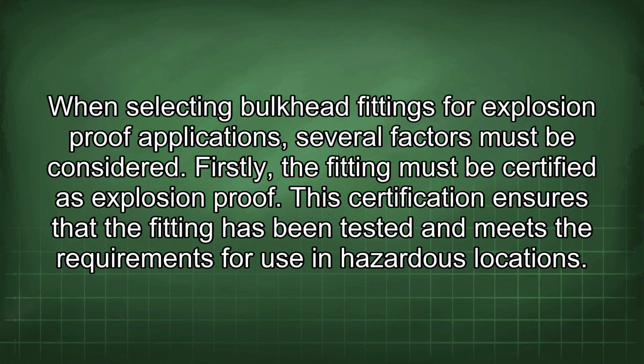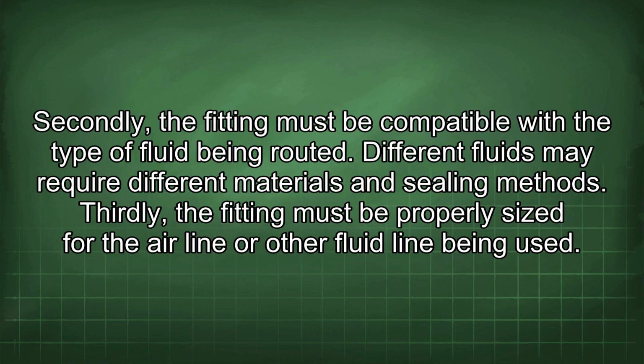When selecting bulkhead fittings for explosion-proof applications, several factors must be considered. Firstly, the fitting must be certified as explosion-proof. This certification ensures that the fitting has been tested and meets the requirements for use in hazardous locations. Secondly, the fitting must be compatible with the type of fluid being routed. Different fluids may require different materials and sealing methods.